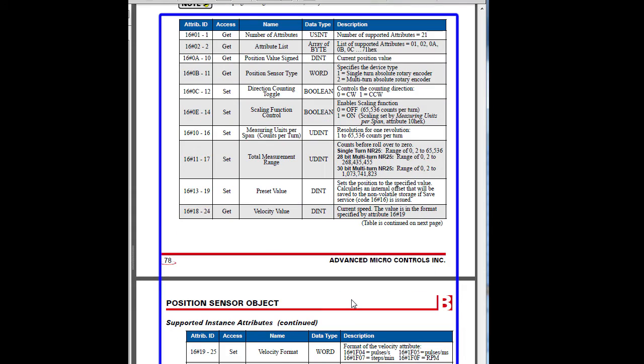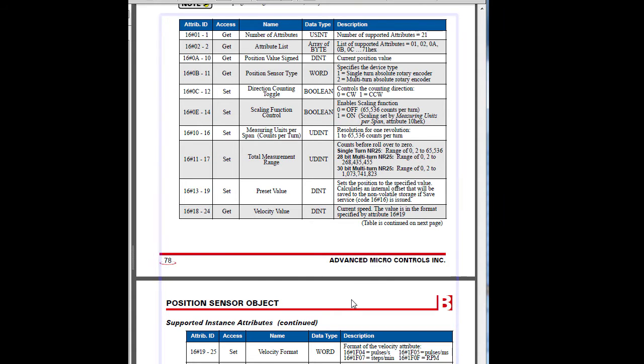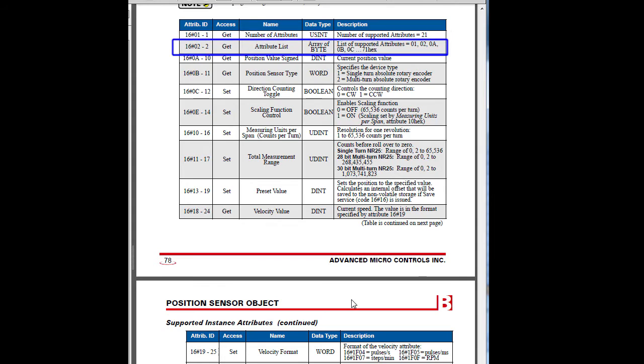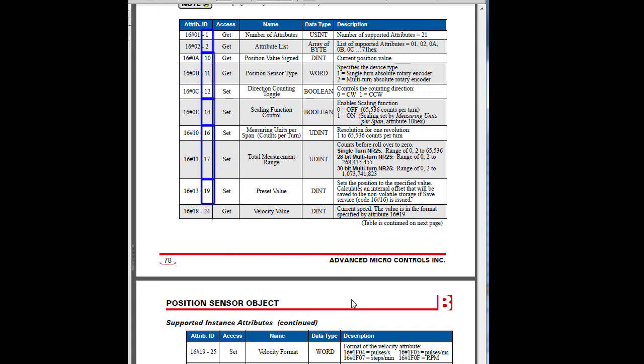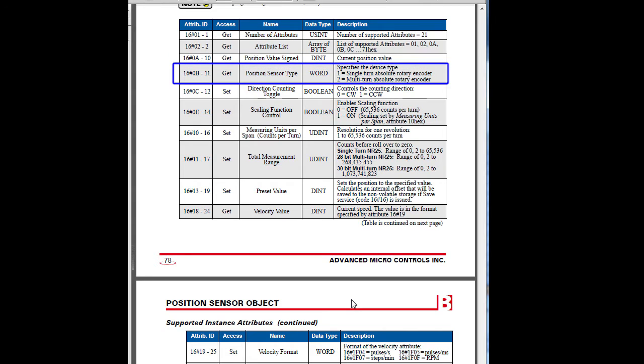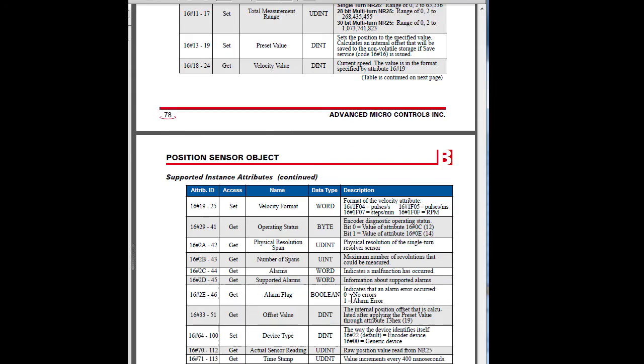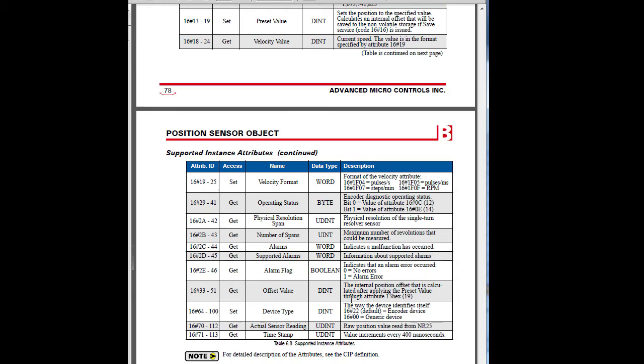And here's the one Ethernet IP position sensor object and all of its attributes. Looks like we can ask it for the total number of attributes, a list of which attributes are supported, notice that they go from 1 to 2, then 10, 11, 12, etc. So not all of the attributes are used here. We can get the current position and the type of the device, specify the counting direction, etc. There's lots of things we can do via Ethernet IP with an encoder.